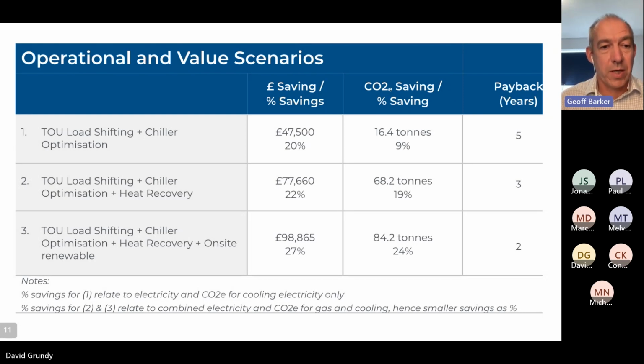The second tier adds heat recovery, which brings a considerable set of other benefits - you can recover heat off the higher temperature part of the chiller system, the de-superheater, where you can store probably 70 degrees or so of water, typically at the rate of the mechanical work on the compressor, storing a reasonable amount of heat. Similarly, if you avoid using a cooling tower, you can store the condensing heat at a lower grade. Using that heat off the system increases overall efficiency considerably.